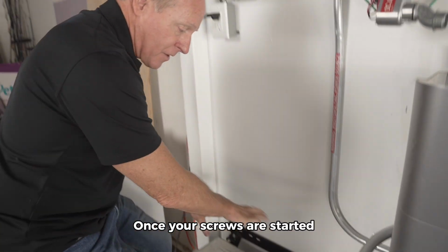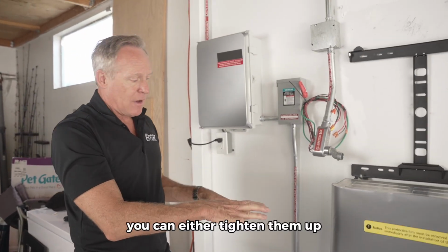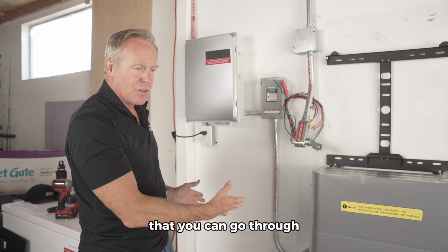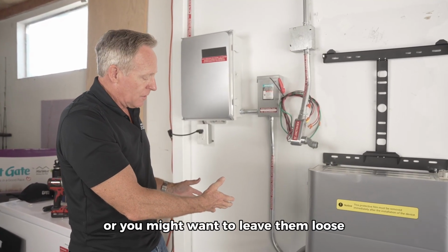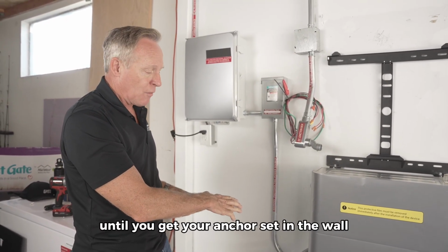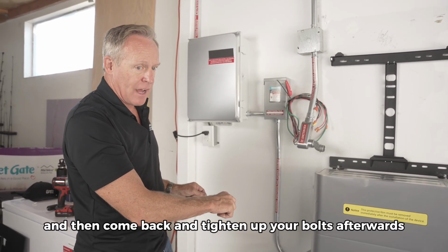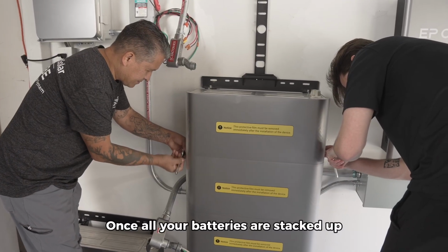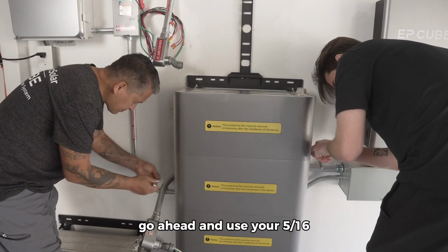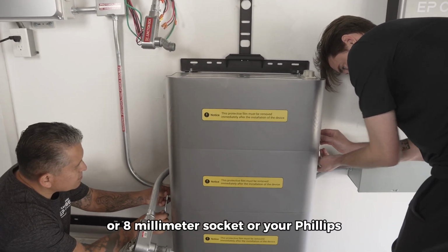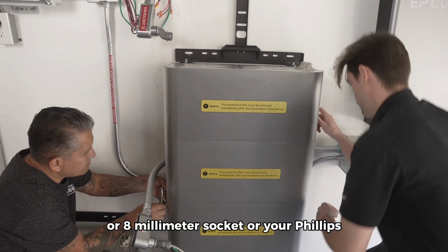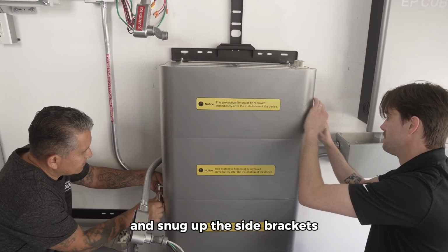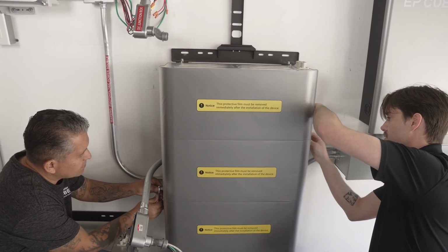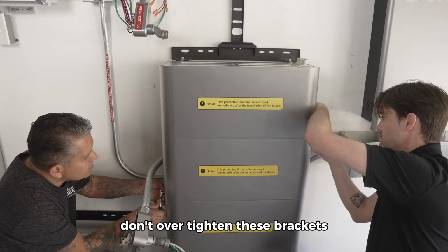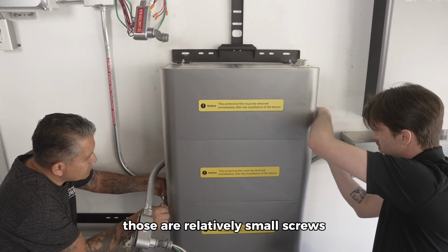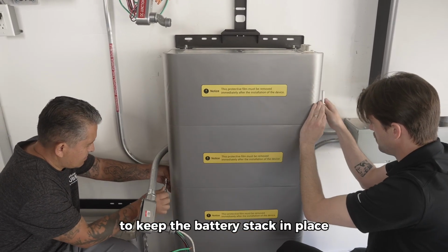Once your screws are started, you can either tighten them up if you're going to use an anchor that you can go through, or you might want to leave them loose until you get your anchor set in the wall and then come back and tighten up your bolts afterwards. Once all your batteries are stacked up, go ahead and use your 5/16 or 8mm socket or your Phillips and snug up the side brackets. Make sure they're all nice and tight. Don't over tighten these brackets. Those are relatively small screws, and these are just a safety to keep the battery stack in place.